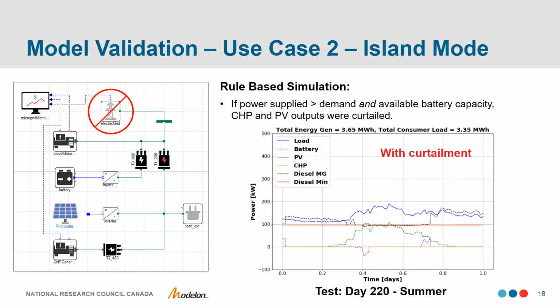In order to resolve this, we introduced curtailment into the model. And by curtailment, in this case, what we mean is taking the CHP system offline and curtailing any excess PV power. As you can see, with curtailment, the diesel generator tracks much more closely to its minimum operating constraint.